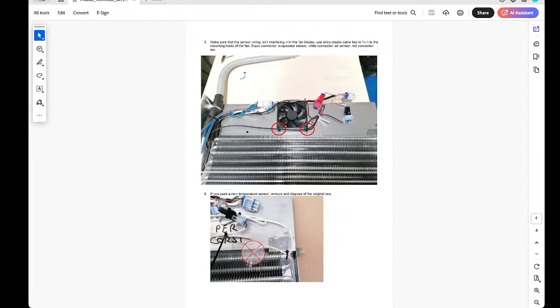So this tech bulletin is one of the new ones. This has to do with fluctuations of temperatures and also ice production. So this is kind of an oddball situation. They share a condenser, two different evaporators, two compressors. The fact that they share a condenser means if one section is struggling, like if that freezer section is struggling with the defrost, it's going to take a lot of the capacity of the condenser, and then the condenser is going to get too warm, and then it's going to cause issues with the fresh food section.